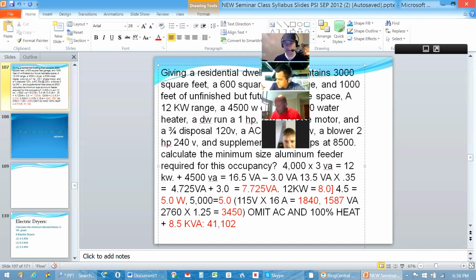So 41,102 VA in the total calculated value there, and that's basically a service calculation. And if they're just asking you for a service calculation, that's all you have to do. You're good there. You don't have to divide by 240.